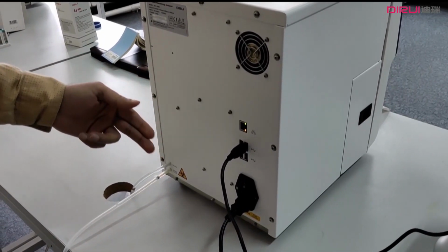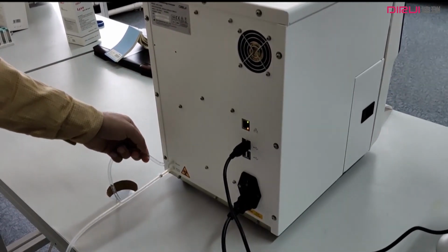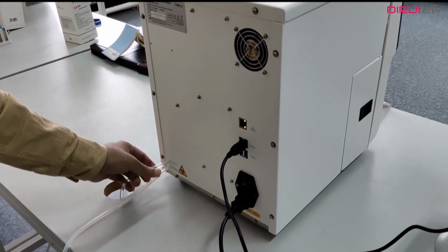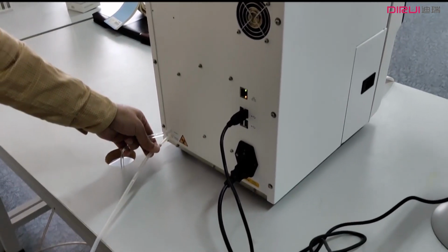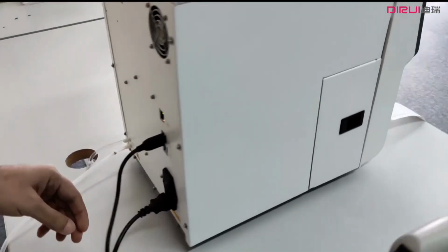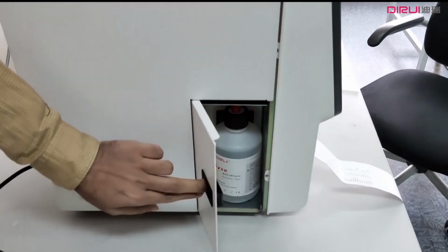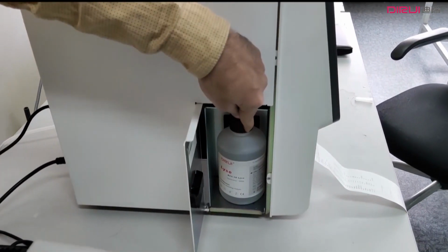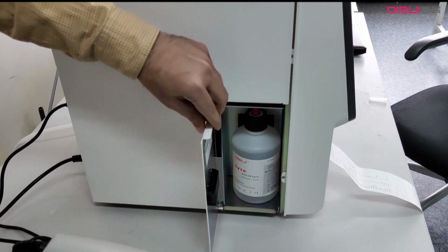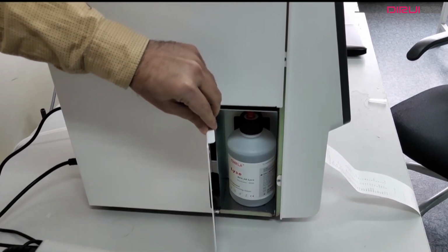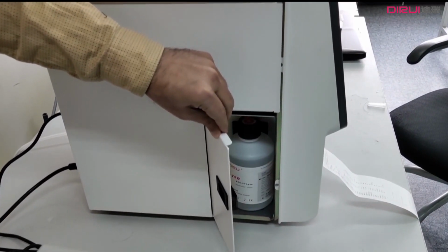One reagent is outside of the machine, there is diluent. Here you connect that reagent and this pipe is for waste. The second reagent is connected inside the machine. You can see its name is lyse. And before starting this machine, you need to make sure all of the connections are well connected.